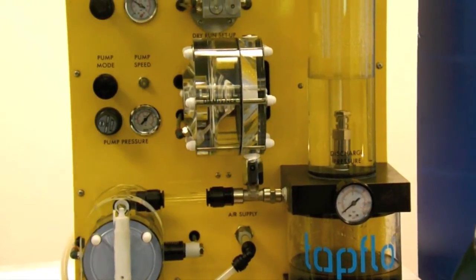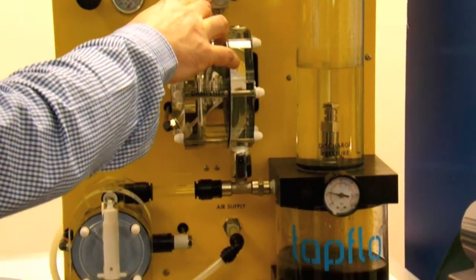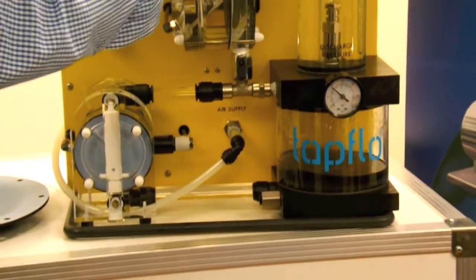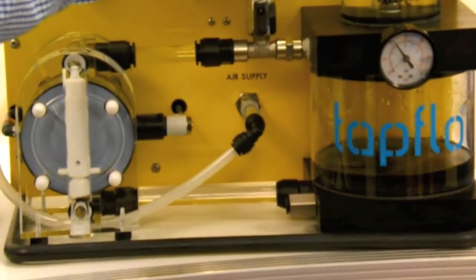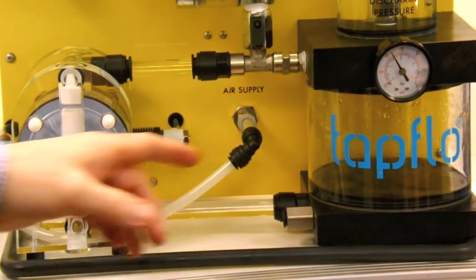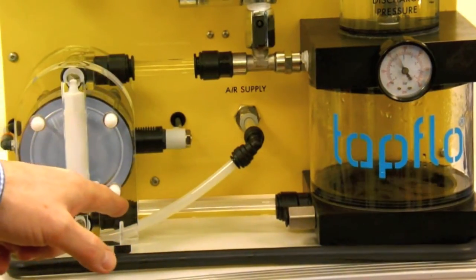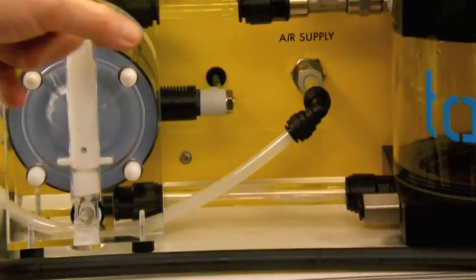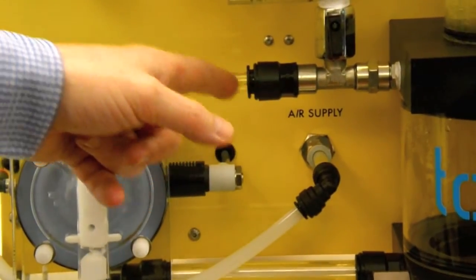So now when I prime the pump by pressing in the button and holding it, the pump will run now until it starts to dry run. So here you will see the pump starts to dry run and you will see bubbles coming through the suction pipe and up through the pump. The discharge pressure falls away, drops below 20 psi and the guardian unit trips the pump out.